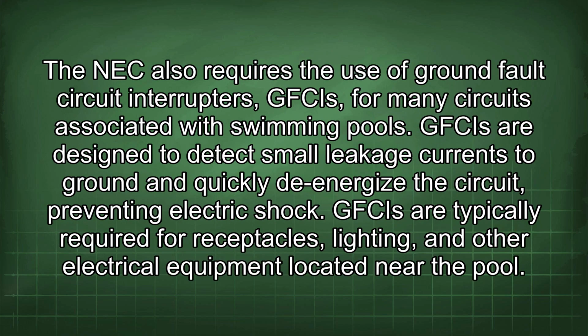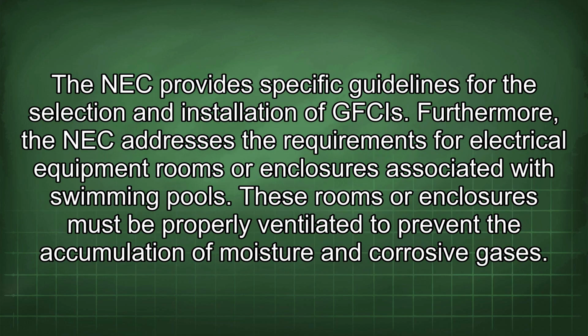The bonding conductor must be of the appropriate size and installed according to the NEC requirements. The NEC also requires the use of ground fault circuit interrupters, GFCIs, for many circuits associated with swimming pools. GFCIs are designed to detect small leakage currents to ground and quickly de-energize the circuit, preventing electric shock. GFCIs are typically required for receptacles, lighting, and other electrical equipment located near the pool. The NEC provides specific guidelines for the selection and installation of GFCIs.